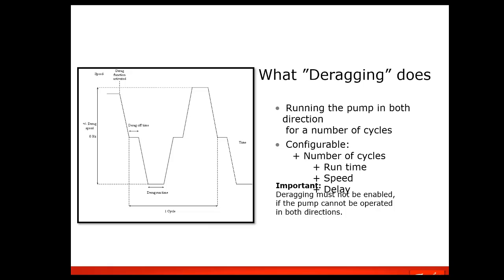What the deragging does, if anything, while trying to run the pump, it will cycle back and forth. It will go forward for a little while, it will go backwards, and you can set the timing as well as how long it will run, what speed it will run, and also the dwell time between forward and backward function. Important to note is that this can only be used on a pump that can be run in both directions. So pumps that can't go backwards, this feature cannot be used then.